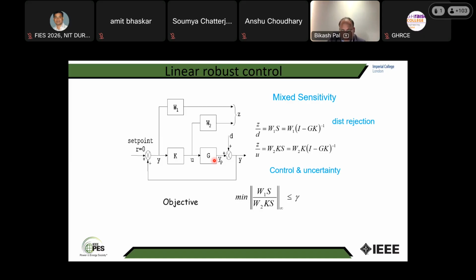And if the number of circuits change, naturally that also will impact these transfer functions. If the characteristics of the demand changes, that will also impact. But if you can pick up the right output signal where you observe the oscillation, like the power flow, right? I was saying, say you have an analog power meter at the substation control room in Bokreshwar, which has got, say, a couple of 500 megawatt. So if that power meter needle is moving like this, so there that oscillation is visible. So that can be your output. And then input is where you can influence this control to be, oscillation to be damped out.